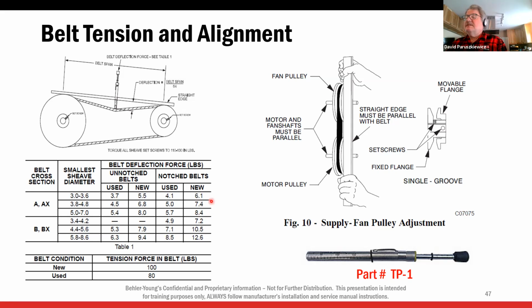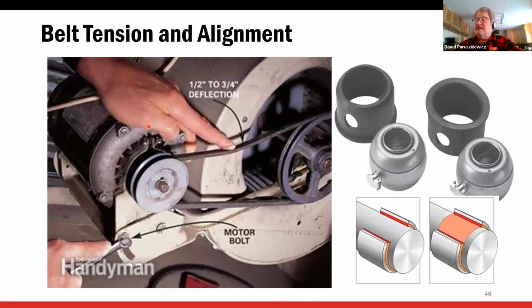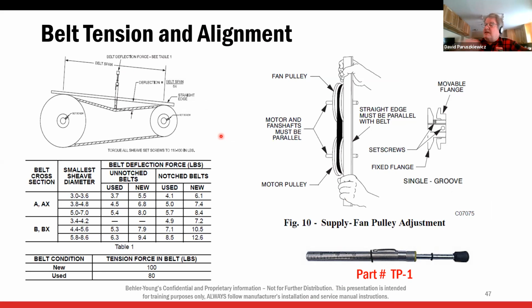What that means is I'm going to take this little tool, push it down on the belt, and put a straight edge here. That's the deflection I should have on this gauge. The 7.4 is the tension. And guess what? That belt is going to be tight. It sure as heck is not going to be like this. Not even close. So you want to properly tension your belts. Get a hold of this tool. For alignment, obviously you should use a straight edge to get the belts aligned properly. Sometimes you get a really thick pulley, so use some common sense. You should be doing the edge of the belt if you can.